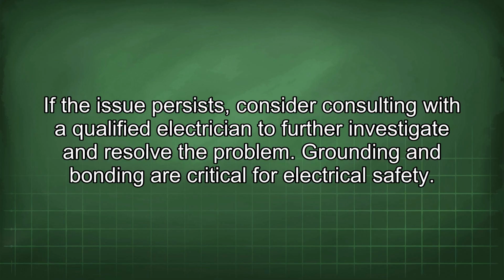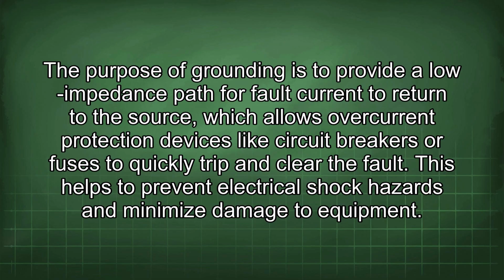Grounding and bonding are critical for electrical safety. The purpose of grounding is to provide a low impedance path for fault current to return to the source, which allows overcurrent protection devices like circuit breakers or fuses to quickly trip and clear the fault. This helps to prevent electrical shock hazards and minimize damage to equipment.